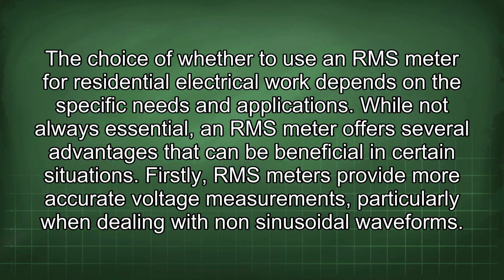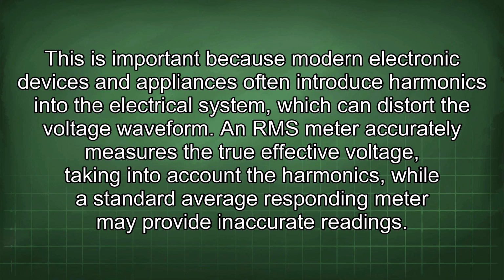Firstly, RMS meters provide more accurate voltage measurements, particularly when dealing with non-sinusoidal waveforms. This is important because modern electronic devices and appliances often introduce harmonics into the electrical system, which can distort the voltage waveform. An RMS meter accurately measures the true effective voltage, taking into account the harmonics, while a standard average responding meter may provide inaccurate readings.